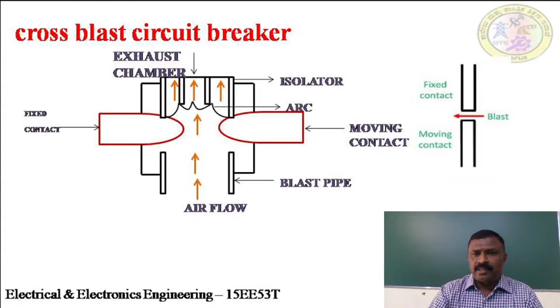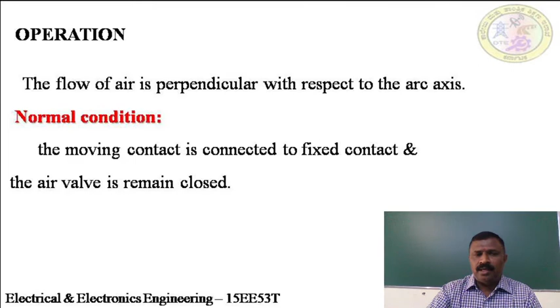Now the operation of the cross blast circuit breaker. Here we allow the high pressured air perpendicular to the arc axis. Again, the operation can be divided into two classifications: the normal condition and the abnormal condition. During the normal condition, the moving contact and fixed contact are held together and the air valve remains in the closed position. When you get an abnormality, when a fault occurs, the moving contact gets separated from the fixed contact. When these two contacts separate, an arc is produced between the contacts.